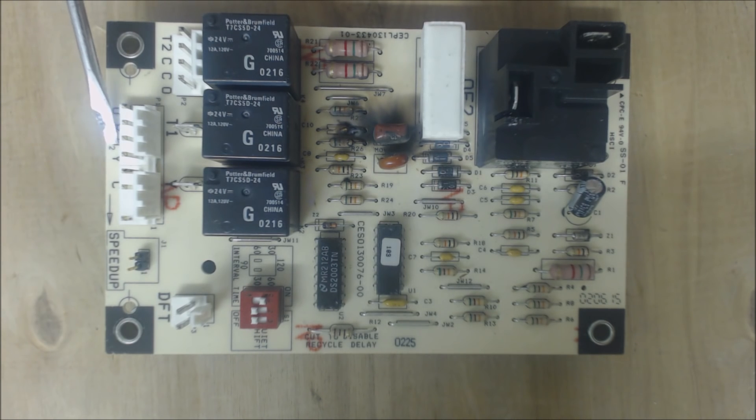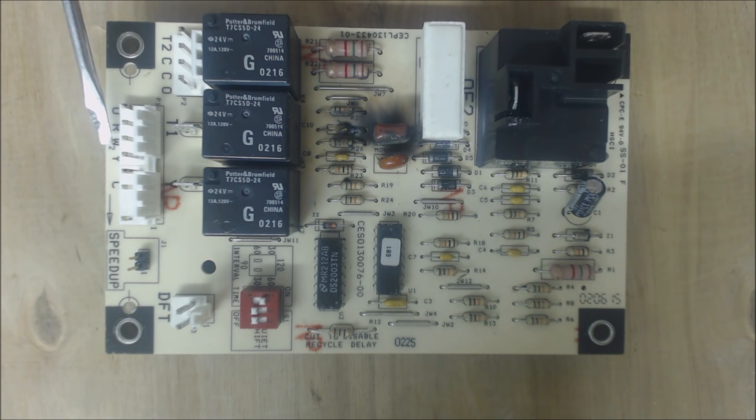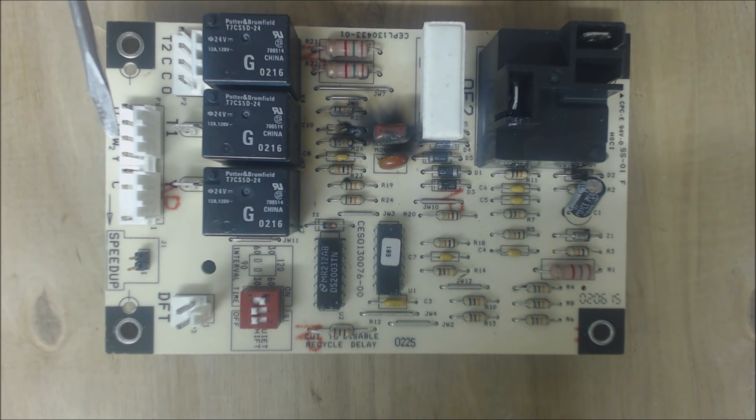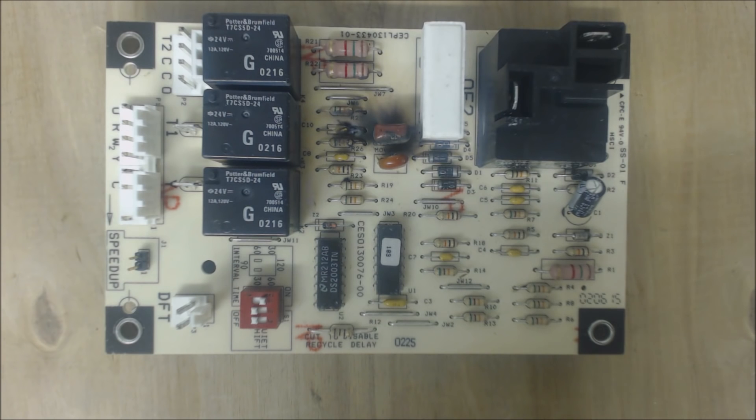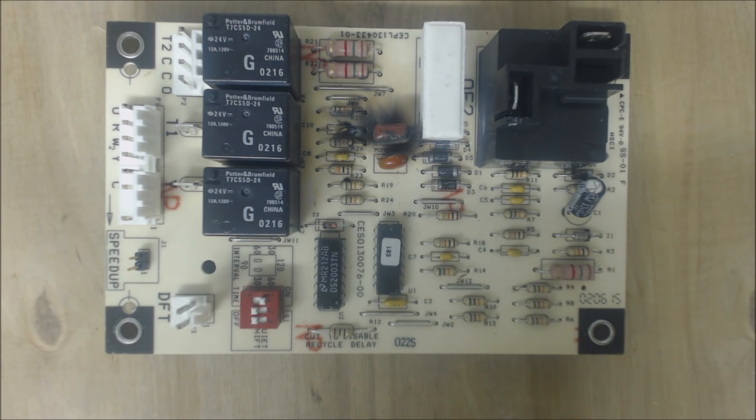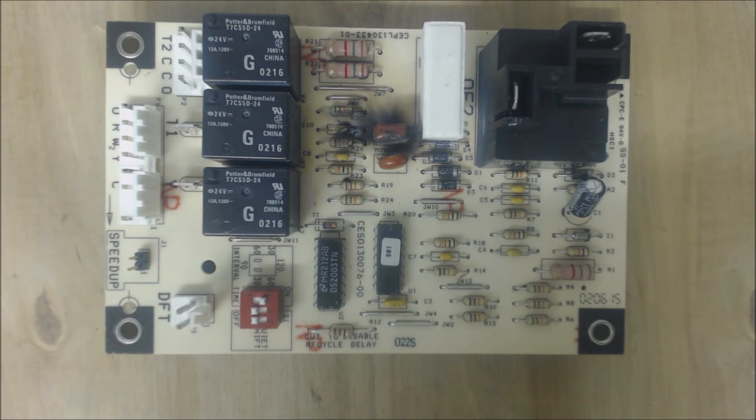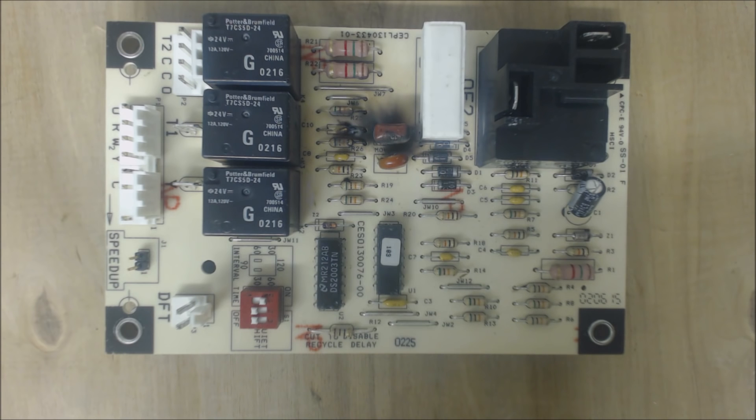Now W2 is the only wire that is an output. W2 is an output from here, letting the indoor unit know that this is in defrost right now, and that you would be powering the auxiliary heat. So that goes to the W terminal on the furnace or the electric heat strips on an air handler.